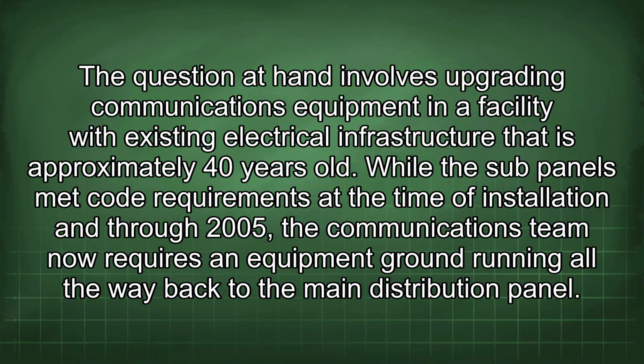The question at hand involves upgrading communications equipment in a facility with existing electrical infrastructure that is approximately 40 years old. While the sub-panels met code requirements at the time of installation and through 2005, the communications team now requires an equipment ground running all the way back to the main distribution panel.